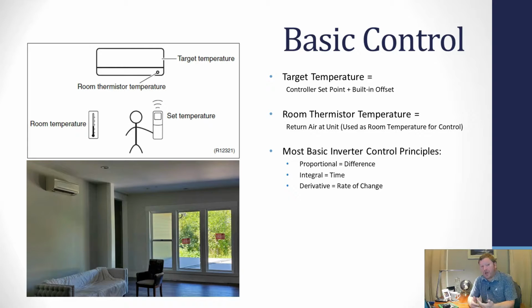Now, the I stands for integral. That's your time-based factor. So how long has that difference of 8.5 degrees been there? Has it been 1 minute? Did you just set it? Has it been an hour? How long has it been? The last part of the calculation is the derivative, which is your rate of change. And this is where the judgment comes into play that tries to not overshoot that target temperature.